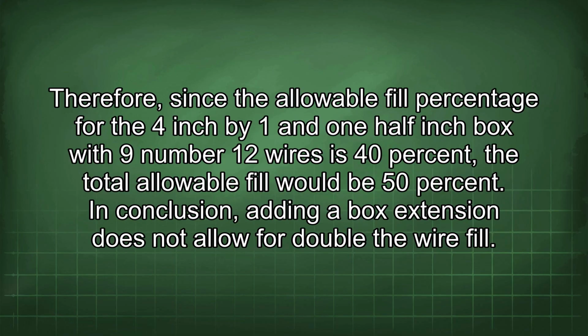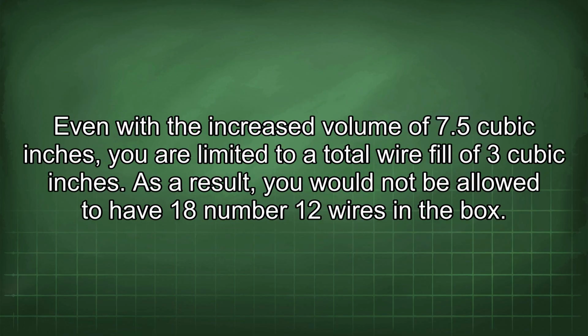Therefore, since the allowable fill percentage for the 4 inch by 1½ inch box with 9 number 12 wires is 40%, the total allowable fill would be 50%. In conclusion, adding a box extension does not allow for double the wire fill. Even with the increased volume of 7.5 cubic inches, you are limited to a total wire fill of 3 cubic inches. As a result, you would not be allowed to have 18 number 12 wires in the box.